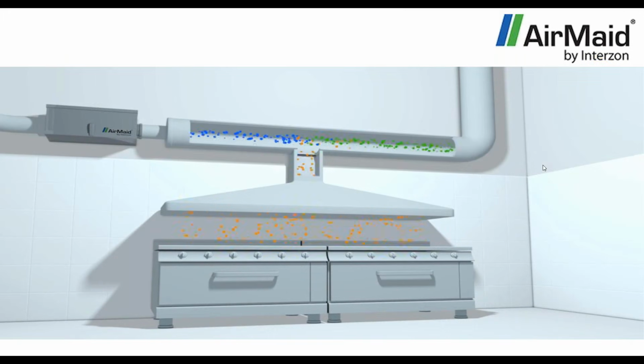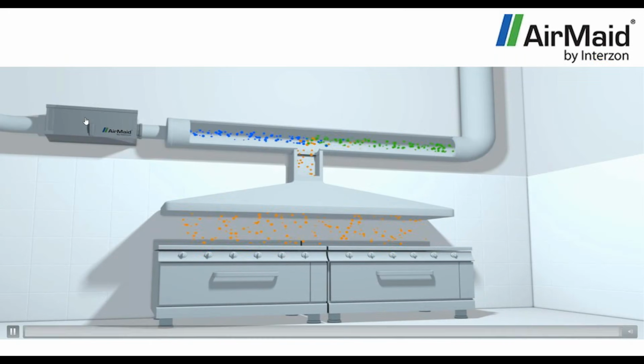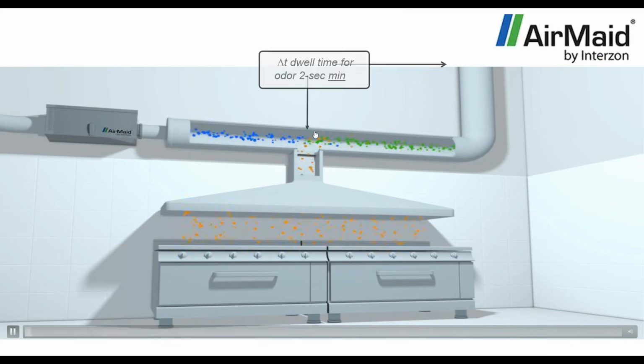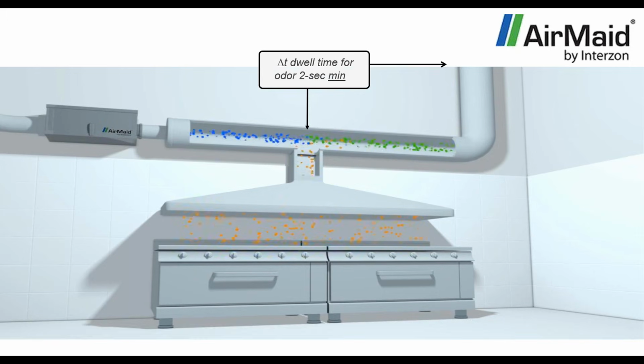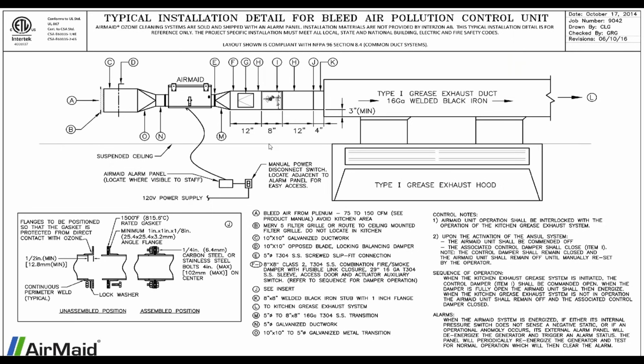So here's an example of how it's installed. You have your hood. Your AirMaid is installed adjacent to the grease duct, and taps into the side of it after it leaves the hood. We want at least a 2-second minimum of dwell time to make sure that we're using up all that ozone with the grease particles. So we have to make sure we have a decent sized grease duct run. We don't want to just go right out the back of the building or something like that. So here's an installation detail for this.